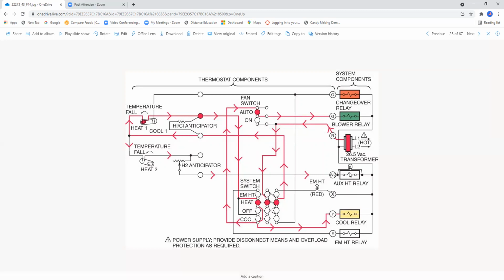If you have auxiliary heat on, same scenario. This light will come on as well, depending on the manufacturer. But this one actually is designed for the emergency heat only. But I have seen the auxiliary heat having a red indicator light to let the customer know. Then of course you got the R terminal, the G terminal for the blower. And now in this particular case, we're utilizing O as the terminal for the changeover relay. On some thermostats for heat pumps, it's going to be the B terminal. And when you install one of these, especially on the electronic thermostats, you have to select either O or B, depending on when it is energized and not energized for heat or cool. And the manufacturers are not all uniform on this, I might add. So I want to make sure you understand that.